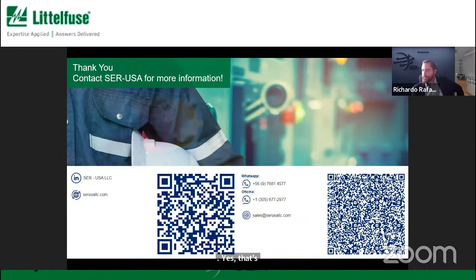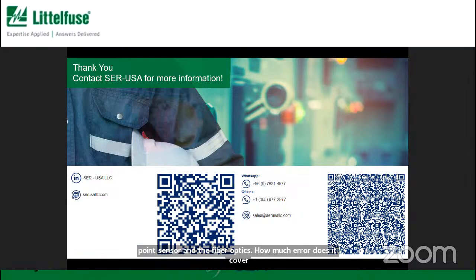Okay, perfect. There is another question from Orly Macias from Ecuador. How much is the range of cover of each sensor, of the point sensor and the fiber optics? How much area does it cover? Sure. The point sensor and the fiber, we say it can see about 2 meters. From where the point sensor is installed, in a half circle, you could see about 2 meters out in all directions. For the fiber, you could see out about 2 meters, again, in a radius around the fiber. And that's the range we give there.